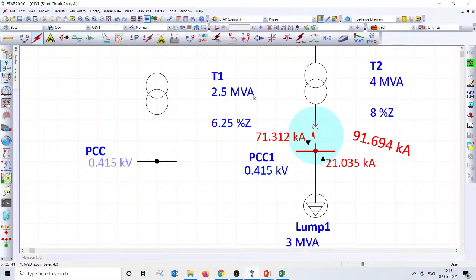A few people may go with 3.15 MVA, and you can go back to IEC 60076. You can go to IEC 60076 and look at the standard transformer ratings. It starts from 25, 40, 50, 63, 80, 100, 125, 160, 200, 250, 315, and so it goes on. So you can pick up the standard ratings of the transformers.